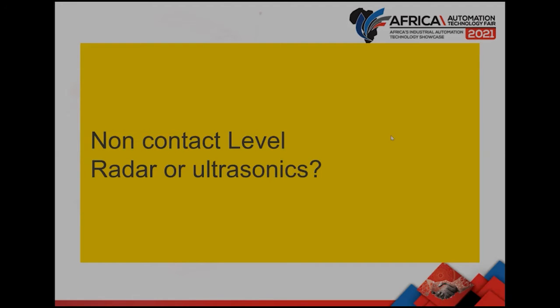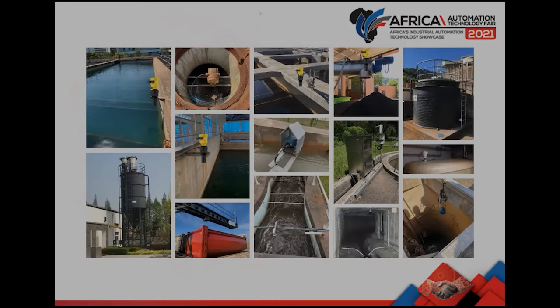So historically, ultrasonic has always been the preferred non-contact level measurement device. I've looked at this picture - the applications shown here are generally quite easy, so most of them are water applications. There aren't many process conditions that will negatively affect them, but there are applications out there that negatively affect ultrasonic level due to the technology used.